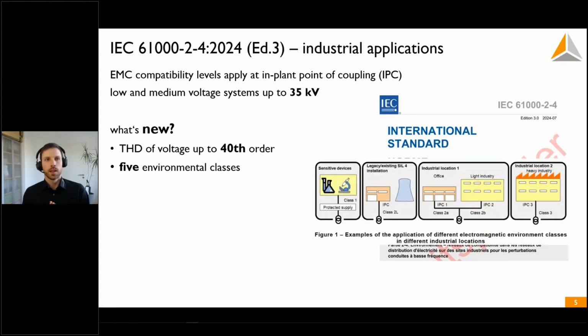Secondly, the second edition had 3 classes. So class 1 for very sensitive devices, class 2 for normal devices that were also connected to the public grid, and class 3 for heavy industry, so welding machines and very big machinery that also produces high emissions.